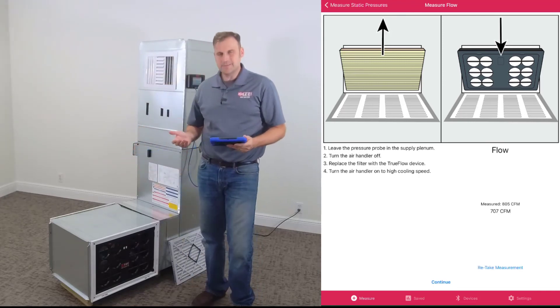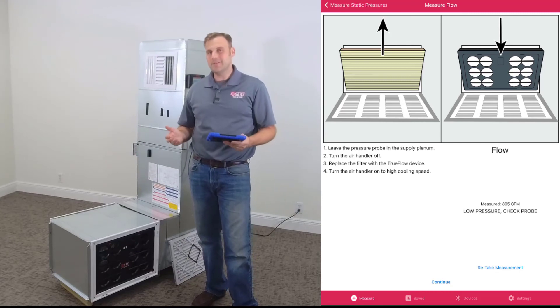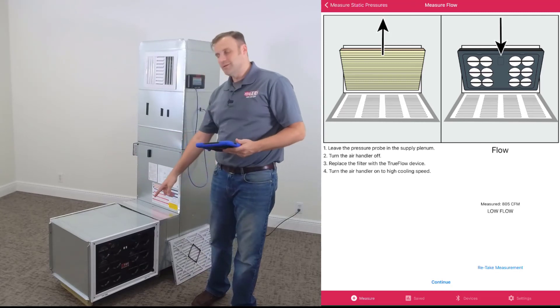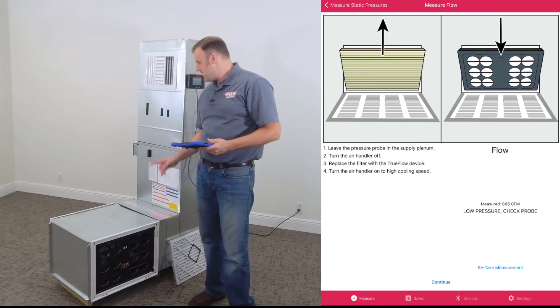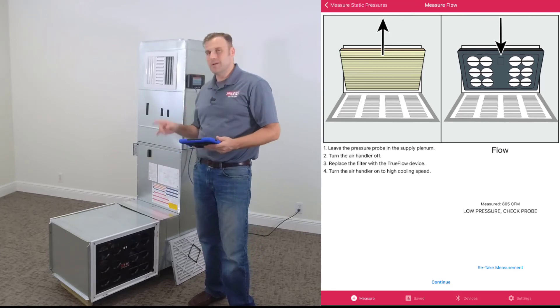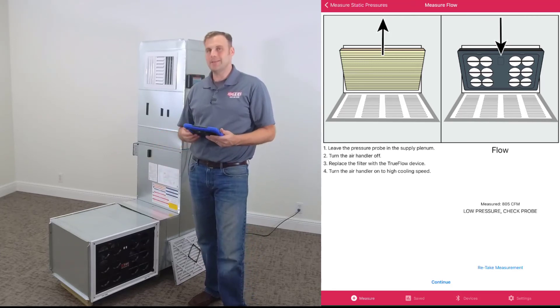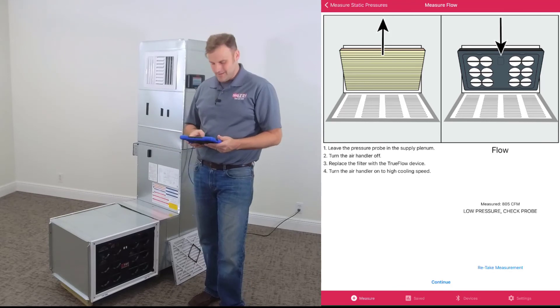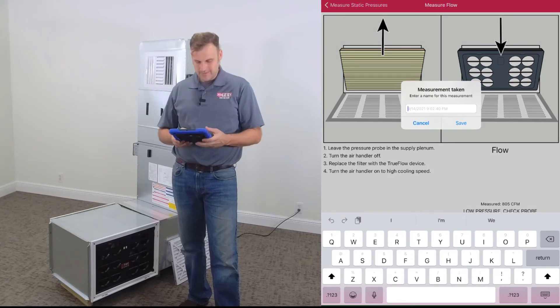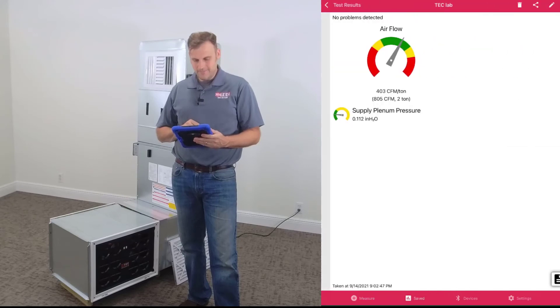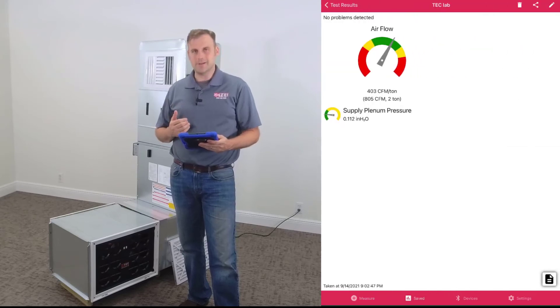The system's moving 805 CFMs with the filter in place because the grid and the static pressure measurements are running a correction factor in the back end of the app to tell you that. Now let's click Continue. We'll call this TEC Lab, click Save, and now we get our diagnostic screen.